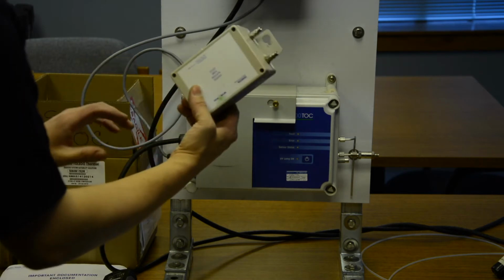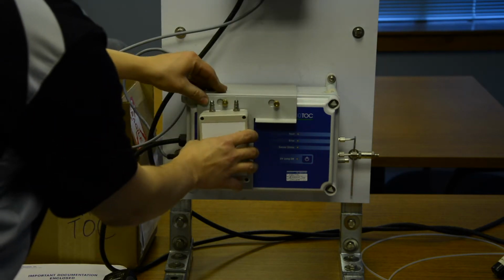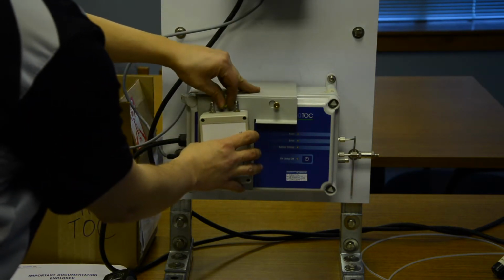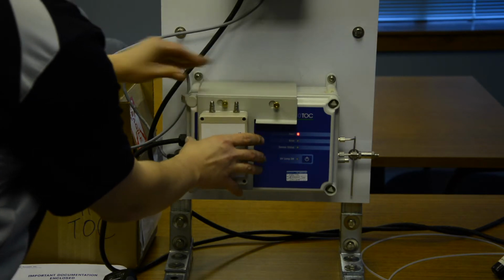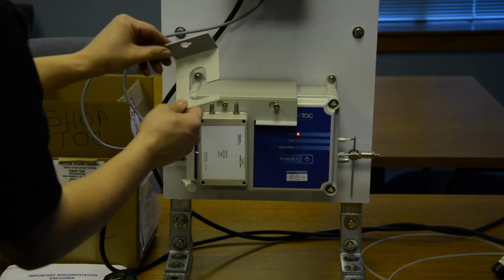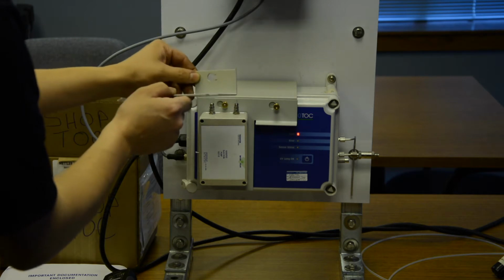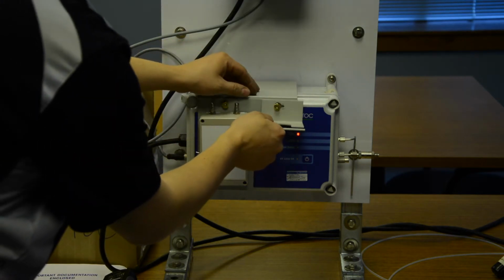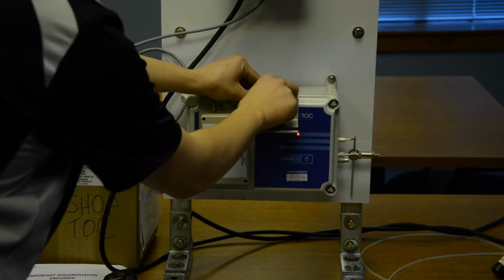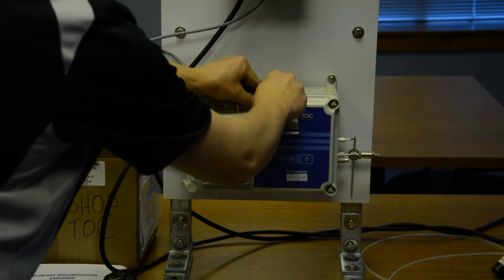Next thing to mount is put the pump on. The pump goes on the left side of the unit and then tighten that screw down. Then you have this piece here, and that's to hold the calibration or the suitability solutions. Place that over top of that screw assembly and tighten down.